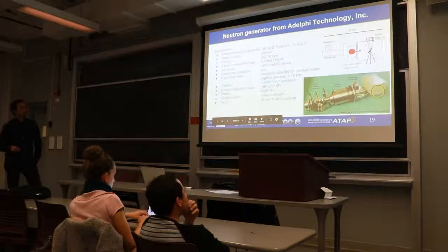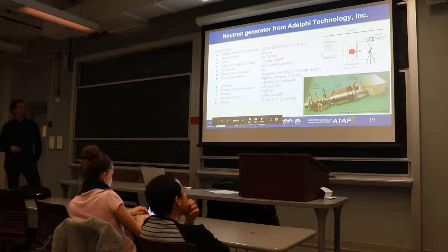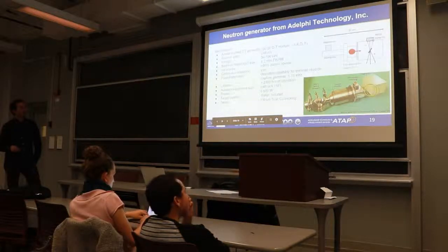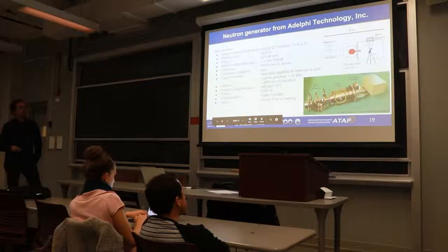In this case, they have a microwave generator right on here. We have a solid-state microwave generator now. We just have a cable coupling in here. This is the main, in here is the plasma chamber. The plasma chamber is biased to positive voltage. So we're actually biasing the ion source so that we can have the target on ground.